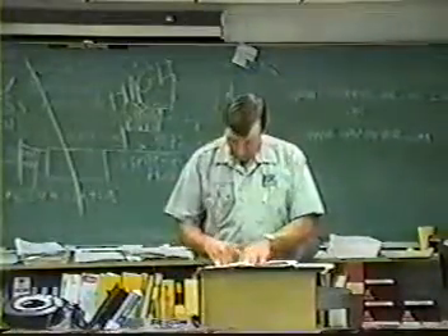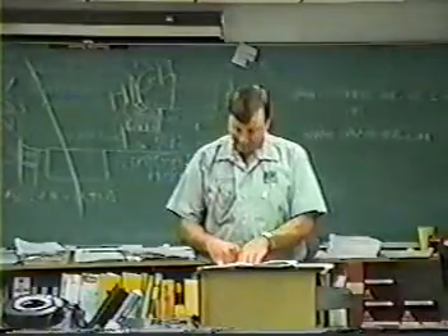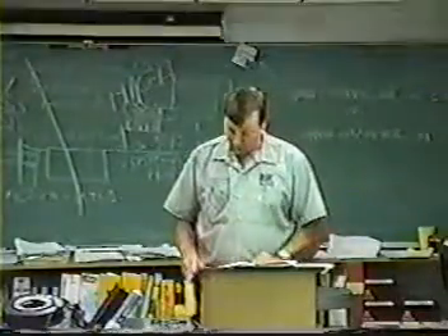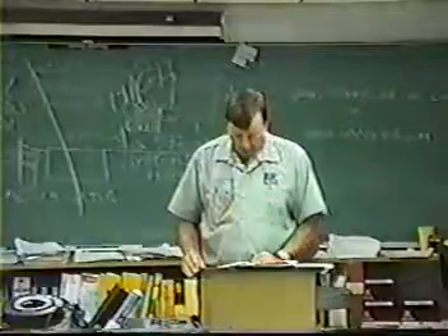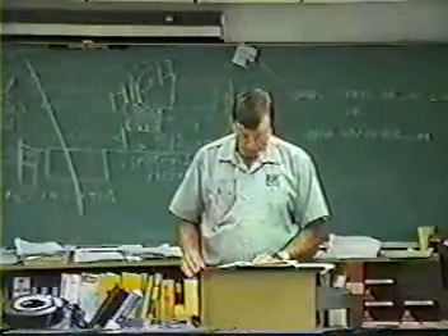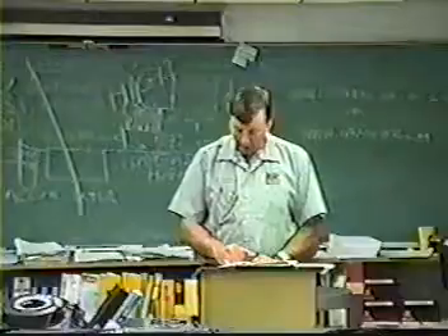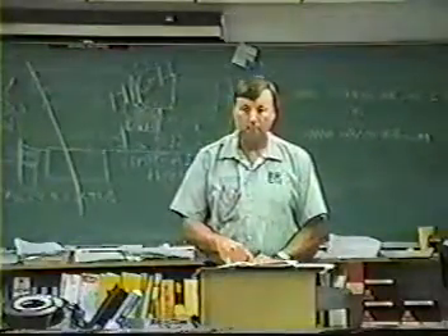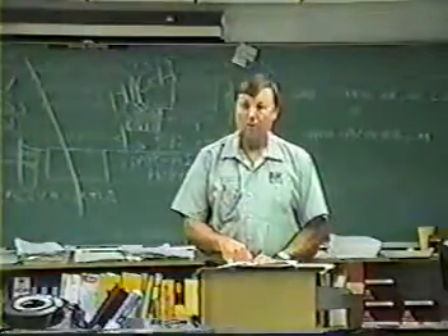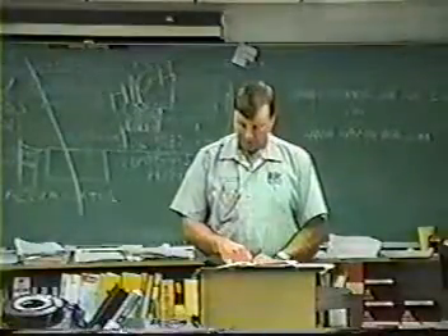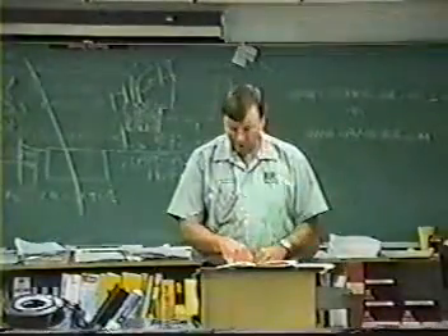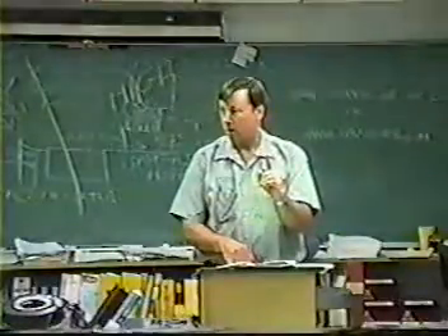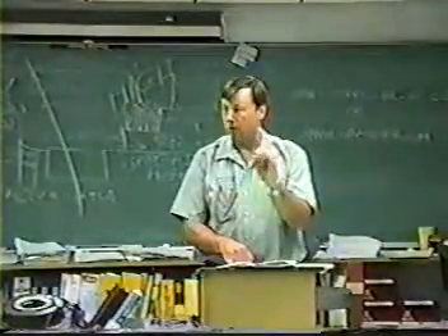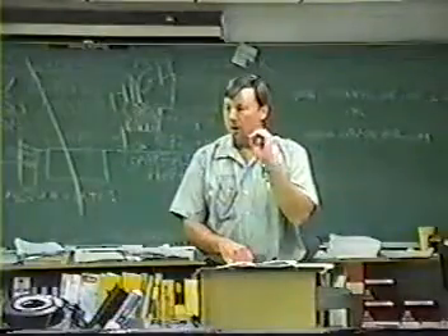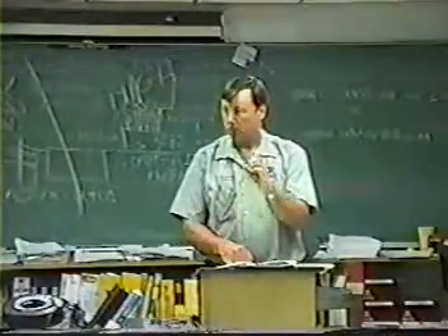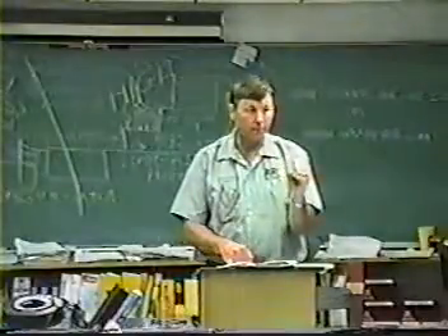Okay, let's move on to number 71. Deep vacuums used for evacuation and dehydration of systems are measured in what? D, microns. Microns. That's why we use our micron meter, because it measures in microns. In this class, we will not hook up a system without hooking up that micron meter, because that tells you if you've got a leak or not. That's the only way we'll pull a vacuum in this class.